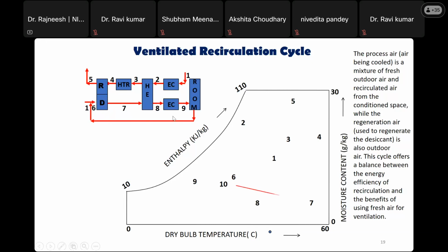The process air that needs to be cooled is a mixture of fresh air coming from the ambient and recirculated air coming from the conditioned space, while the regeneration air used to regenerate the desiccant is also outdoor air. So this cycle offers a balance between the energy efficiency of recirculation and the benefits of using fresh air for ventilation. That is the additional feature.